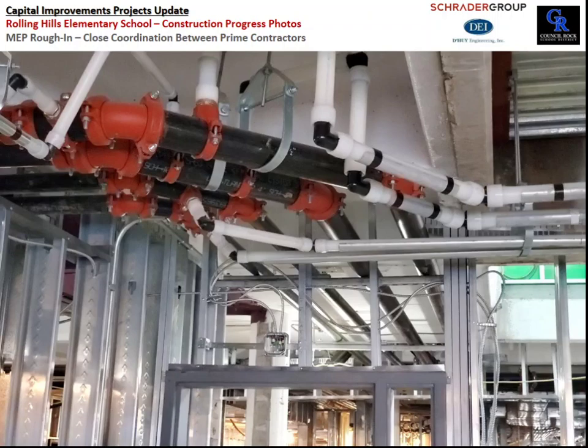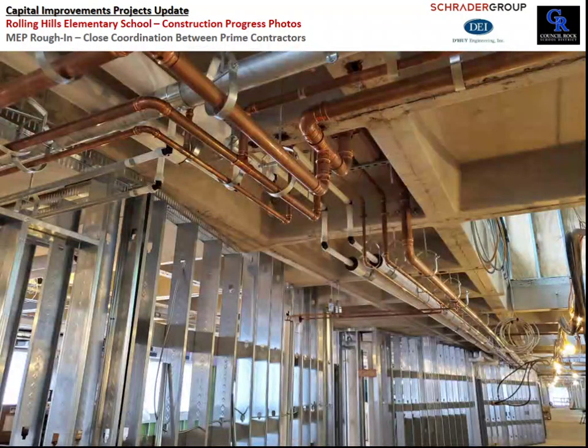When I talk about rough-in and coordination, I mentioned the challenge of coordinating mechanical, electrical, and plumbing work here. You can see all of the utilities. One thing we're taking advantage of is this waffle slab, with these bump-ups. The low area is what we have to be concerned with in terms of hanging the ceiling, but we're going up inside these areas whenever we can to make transitions and avoid lowering our ceilings. Here's another example where you bump up and across instead of sideways, where there might be light fixtures or sprinklers. Everyone has a zone they have to work within to make sure all the systems fit - the electrician has a zone for light, there's hydronic piping for heating and air conditioning, and a sprinkler zone. Everybody has their zone and stays clear of the others. It's a lot of work - we spend a lot of hours measuring and working together.